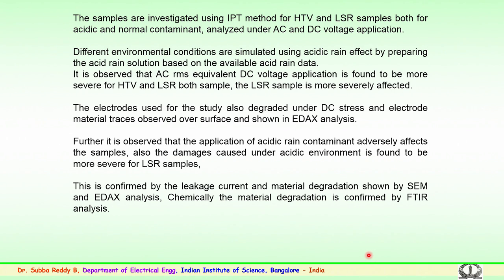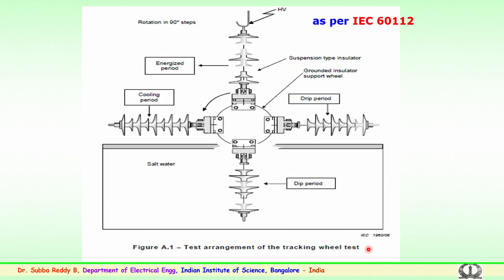This is a very important experimentation and analysis for estimating surface degradation on polymer samples. After the inclined plane and surface erosion studies, the aging of polymer or composite insulators is of utmost importance. Aging consists of three types of experimentation carried out in the laboratory. The first is the salt fog method, applied to the insulator continuously for 1000 hours while electric stress is applied and surface changes are observed.